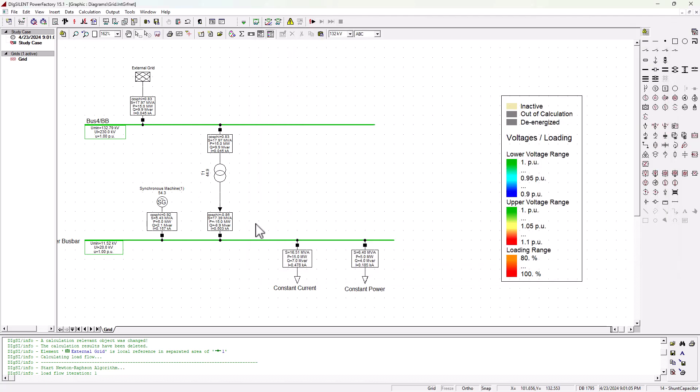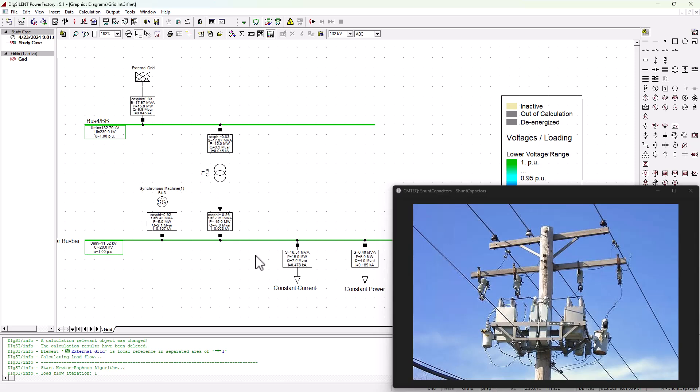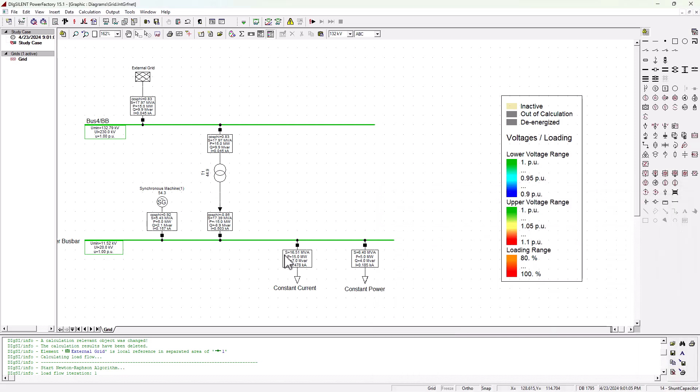All of this just means that the new capacitor that we're going to add here—the shunt capacitor, one of these guys here that we're going to add into the system—it must be about 5 MVA reactive. It must supply about 5.1 MVAR into the system so that the grid power factor can improve from 0.83 to 0.95. So let's go ahead and add that shunt capacitance or that shunt capacitor into our network.